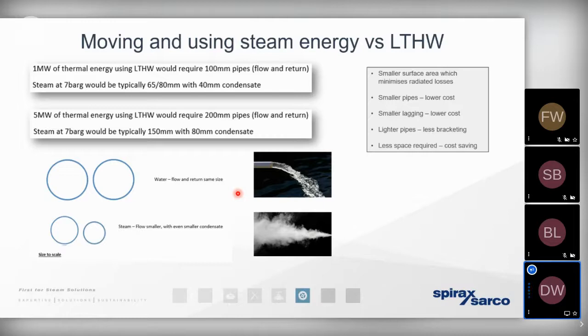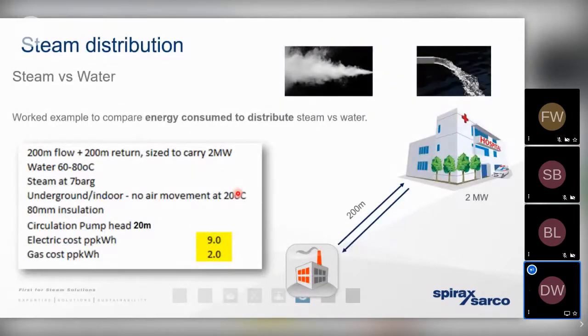But one area that is often overlooked is the distribution costs with steam. So we know that steam as a gas, well, it's not pumped. The steam is going to move from the boiler house to the various processes around site under its own motive energy. It's a gas. It flows in accordance with the pressure drop.